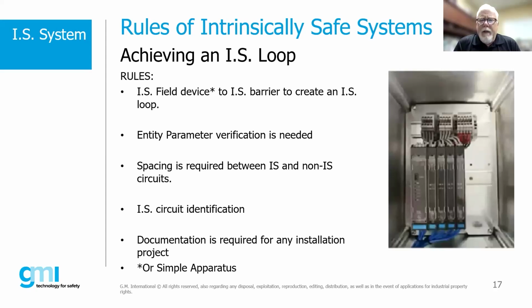Yeah, actually I'm going through this right now where a customer has built some panels for thermocouples, and they could not find thermocouple terminals that were light blue - they were kind of scrambling. I said, well, you've got gray terminals, that's fine by the standard, as long as we indicate with blue wiring or some sort of indication labels that these are intrinsically safe. You could use blue ductwork, or you could do labeling - you don't necessarily need to have everything light blue, but that's what the standard says.